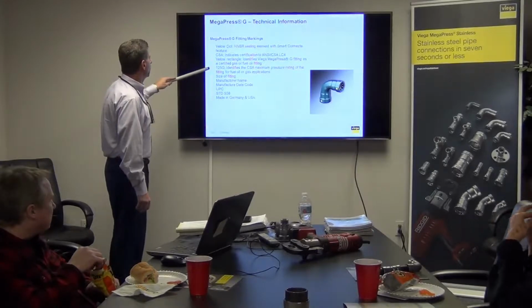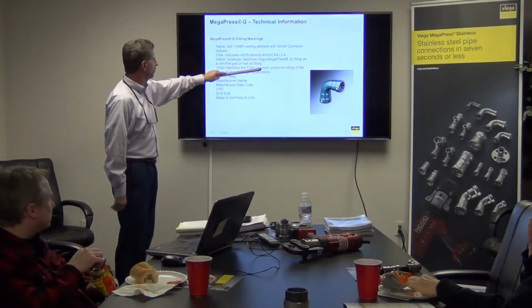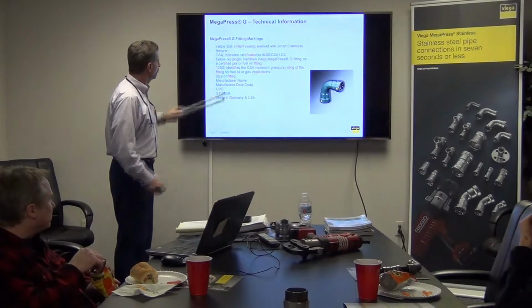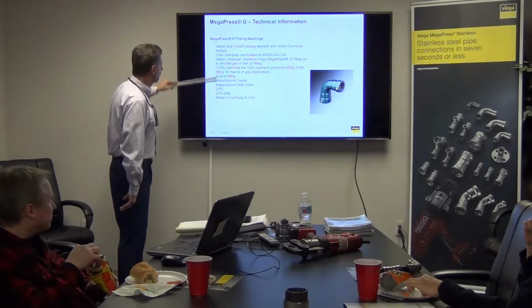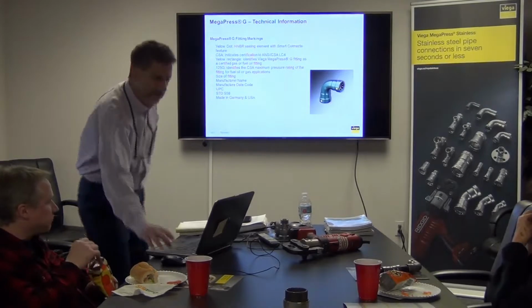Okay, so the 125 identifies the CSA maximum pressure rating for fuel. Remember we talked about that just a few seconds ago. So for your gases, you're looking at 125 PSI, and the size of fittings on there as well. So this is just like the green dot. It has all this information on it, okay, that you'll find somewhere stamped or painted or such.